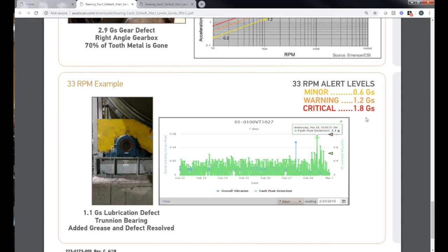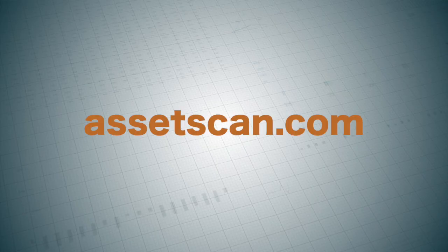Interesting point here is that the asset scan has a store and forward capability. This is a remote location in a steel building, and the customer was concerned the cellular would not get out. We went ahead and deployed this, knowing that he could pull that box out of that steel building, get reception, and the data would flow. In reality, the text message was able to get out from inside this building. It does not need much, doesn't need the full strength that you need for voice, and it will retry to get that data out.